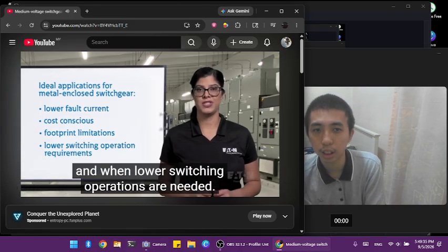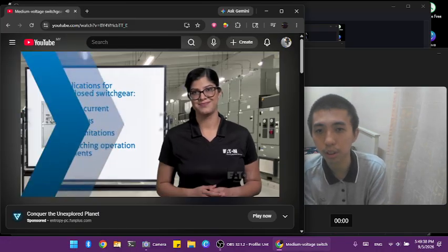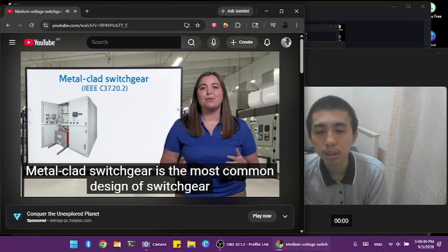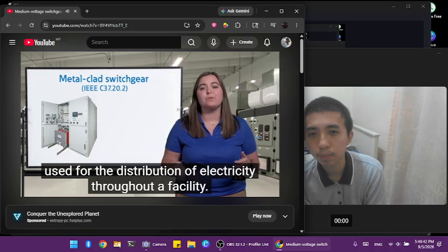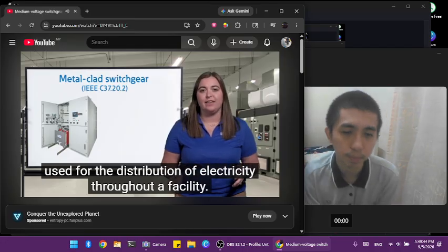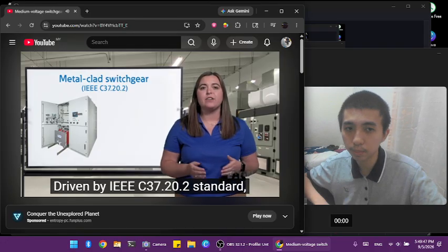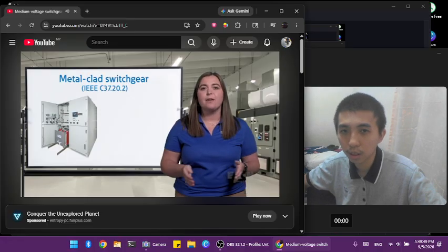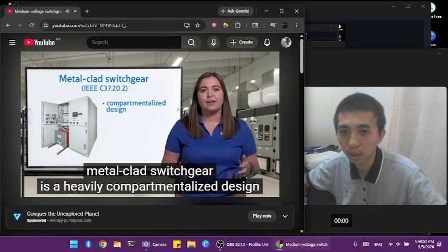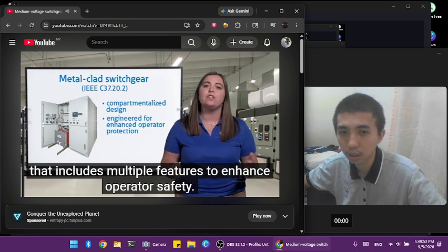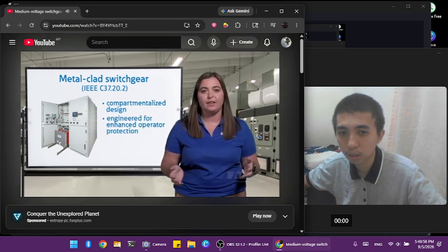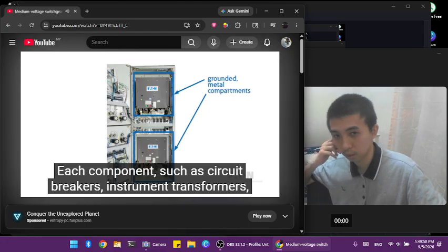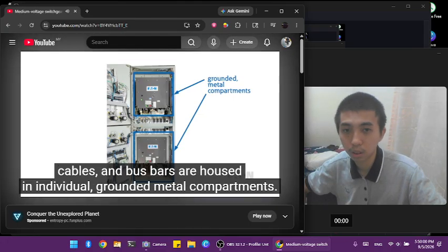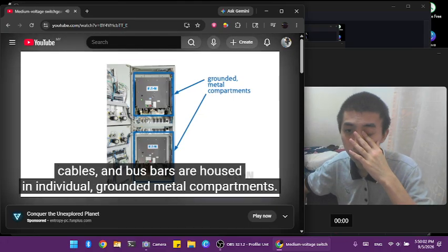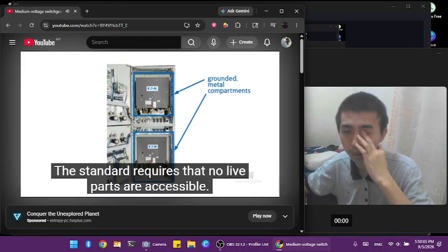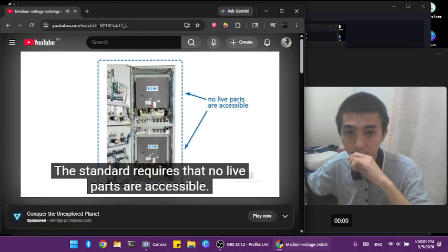And when lower switching operations are needed, metal-clad switchgear is the most common design of switchgear used for the distribution of electricity throughout a facility. Driven by the IEEE C37.20.2 standard, metal-clad switchgear is a heavily compartmentalized design that includes multiple features to enhance operator safety. Each component, such as circuit breakers, instrument transformers, cables, and bus bars, are housed in individual grounded metal compartments. The standard requires that no live parts are accessible.